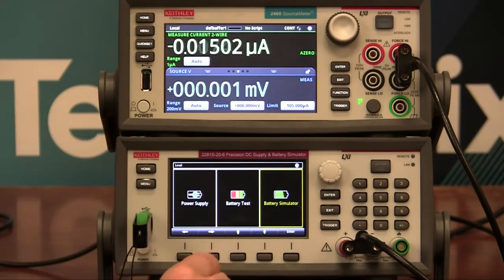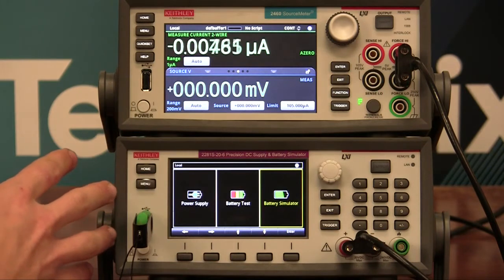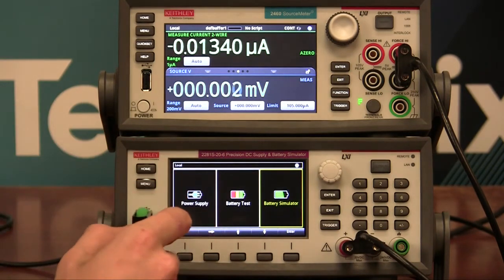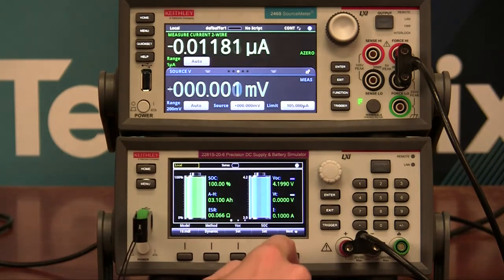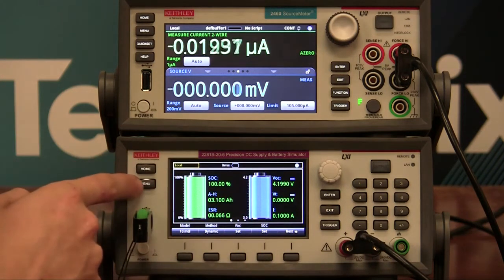The first step is to load a AA battery profile into the 2281S battery. So I've got a profile loaded onto this flash drive, and I'm going to import it into this battery simulator. To do that, go to the battery simulator, go to the menu, and find model.